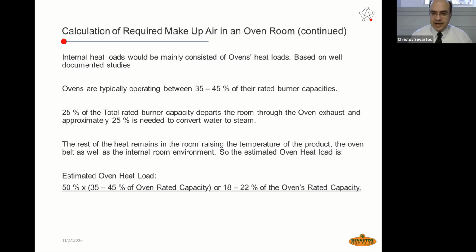So, in general, the estimated oven heat load is 50% of the 35 to 45% of the oven rated capacity. This one is giving us 18 to 22% of the oven's rated capacity. This is how the calculation is made in terms of the internal heat coming from the oven itself.